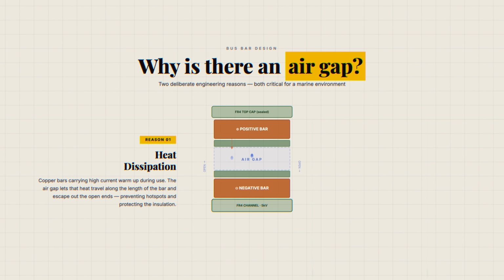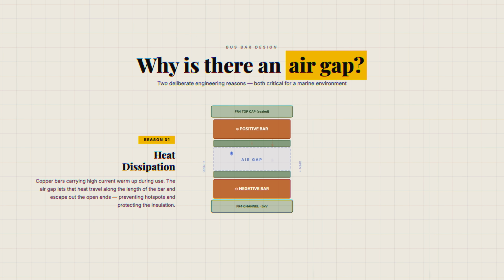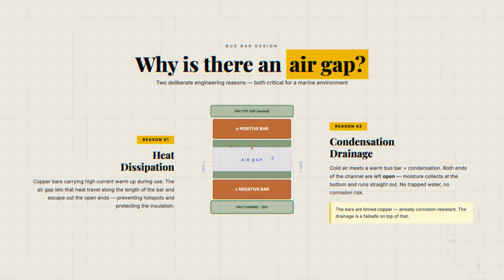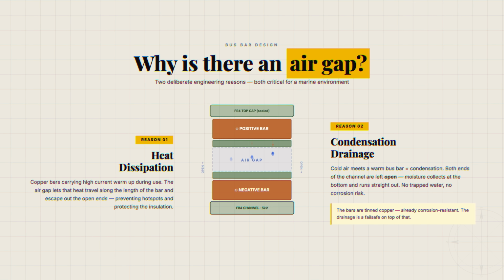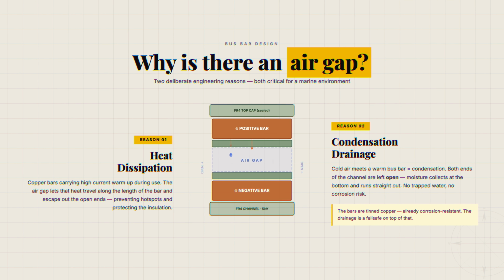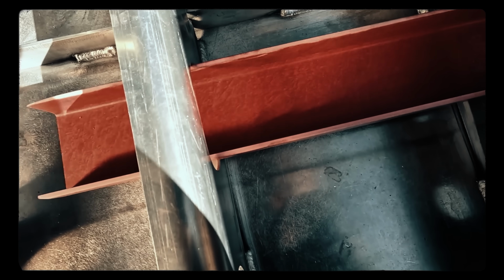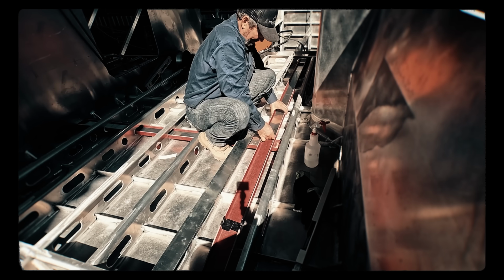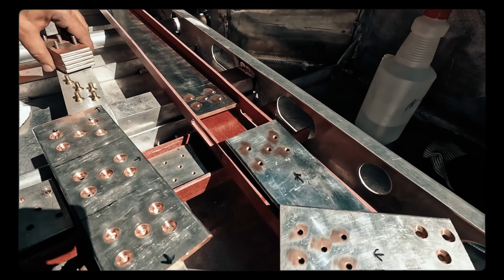The air gap is meant for two purposes. One, I wanted to have a little bit of heat dissipation relief just in case it warmed up. The second is if we happen to get any sort of condensation from having cold air in the bus bar when it warms up, I wanted to have a channel of egress for any water or condensation that might form inside. So the ends of the bus bar are left open, both at the forward and in both engine rooms, so any condensation will just go to the bottom and run out. Since we're using tinned copper, it's very corrosion resistant and good for conduction as well.